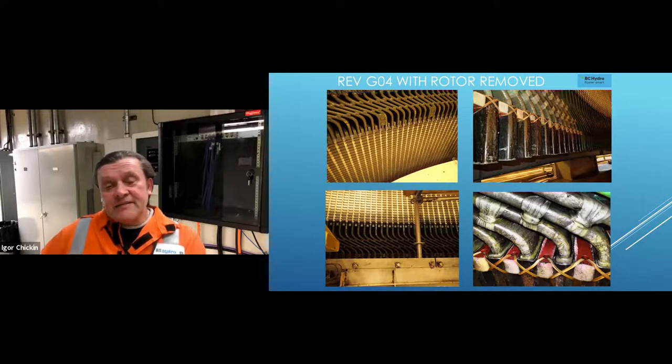And it's not consistent in terms of the voltage stress here. It can be very high and create partial discharge, ionizing the air around it. That ionizing air affects the underlying epoxy resin, which deteriorates as well. So it means that contamination can serve a bad purpose, and it's better to make sure that it's clean. But we did have experience with this on that particular machine. Even when we do a PI test or DC ramp test, we can see that contamination.